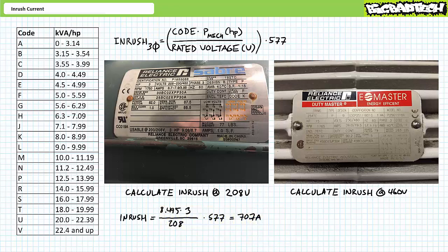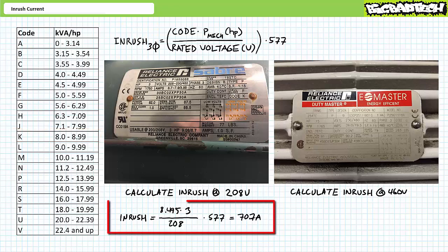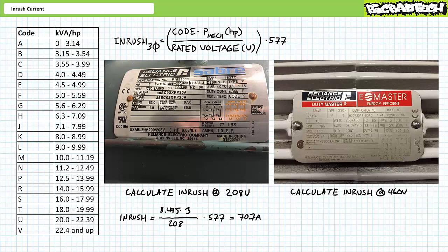The first example features a three-horsepower motor intended to operate using 208-volt three-phase AC in the low-voltage configuration with a locked rotor code of K, meaning it has a kilovolt ampere per horsepower constant with a low of 8 up to a high of around 9. Center of mass is around 8.5. Substituting this value, the power rating, and the rated voltage into the inrush equation results in an estimate of roughly 70.7 amps — roughly 8.1 times the rated current of 8.7 amps in the low-voltage configuration.